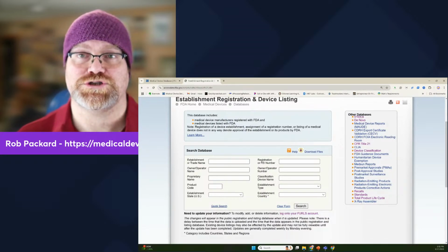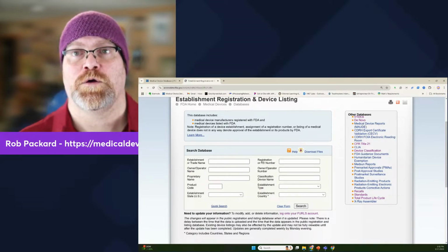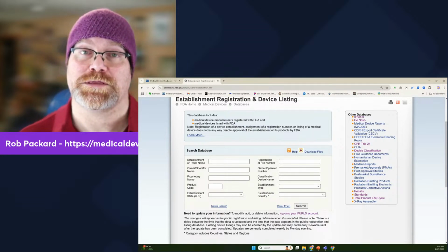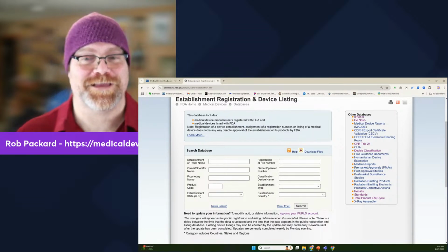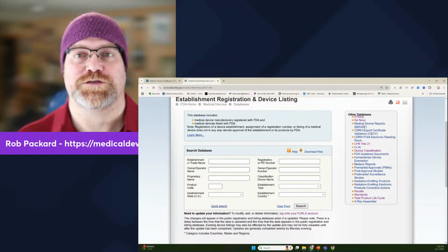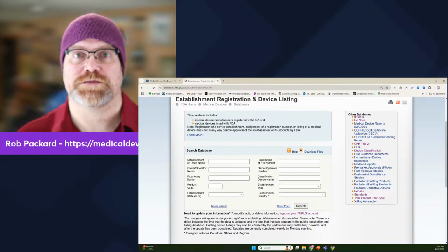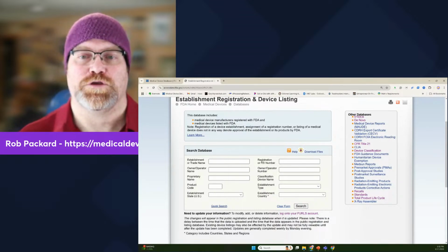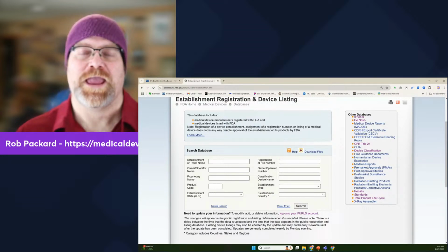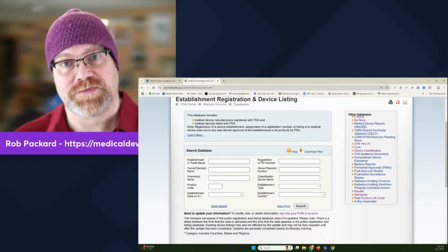Unfortunately, with a 513G, you do not get the choice of saying, well, what if I change this? What would be the answer then? They say, why don't you submit another 513G and we'll tell you. So you can't negotiate with the FDA to come up with the answer you want. You decide what your instructions are, what the intended user is, what the indications are, and you provide that information to the FDA with a device description and draft user manual, and they'll give you what the classification should be in the pathway. So that's the expensive route.